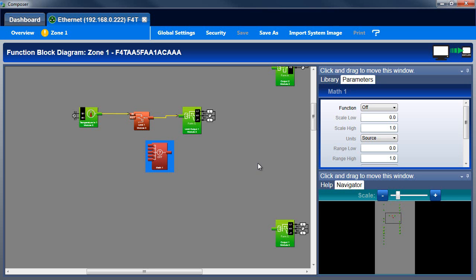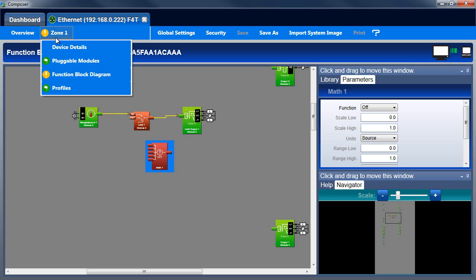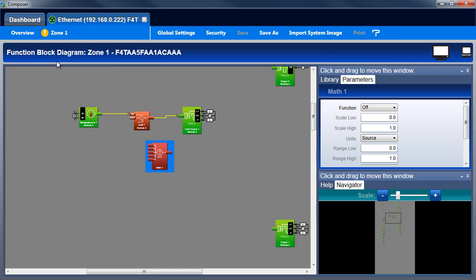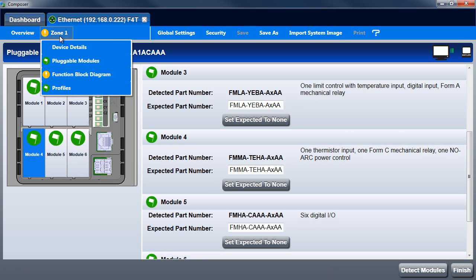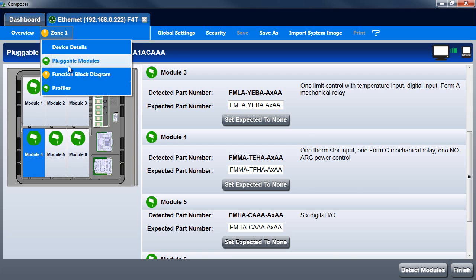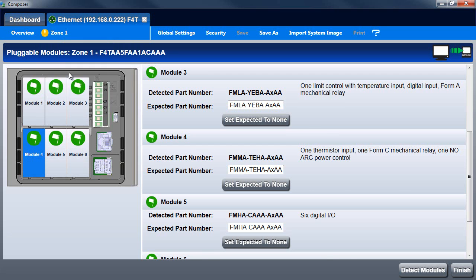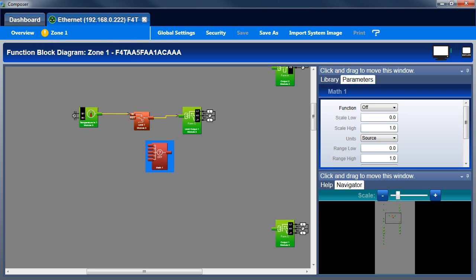If you don't see the inputs and outputs you expect, use the Pluggable Modules view to set the controller to expect the flex modules you plan to use. If you set the controller to expect modules that aren't yet installed, the inputs and outputs for those modules will appear in the function block diagram, however the application won't turn any outputs on until the expected modules are detected.